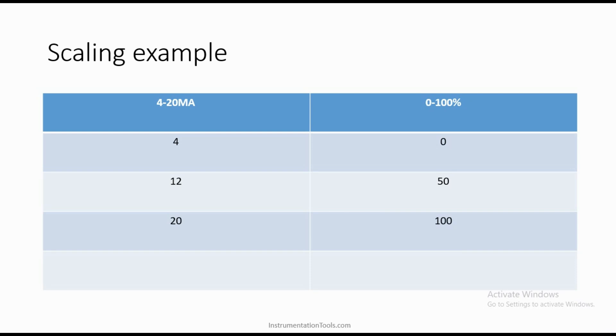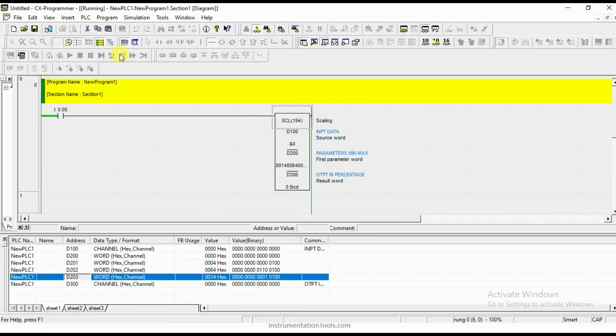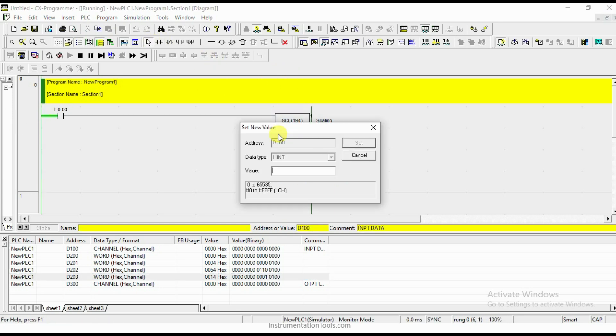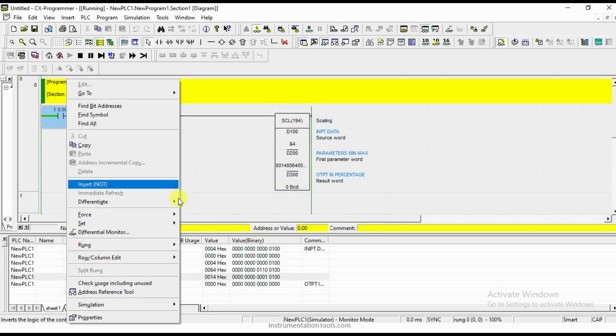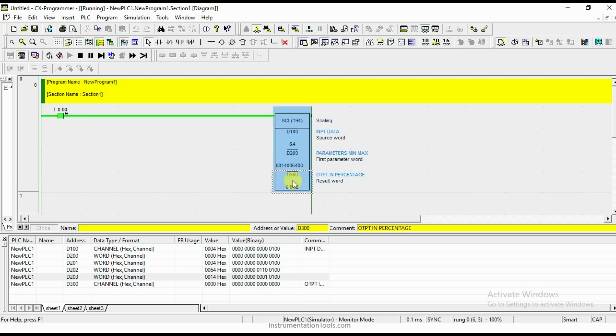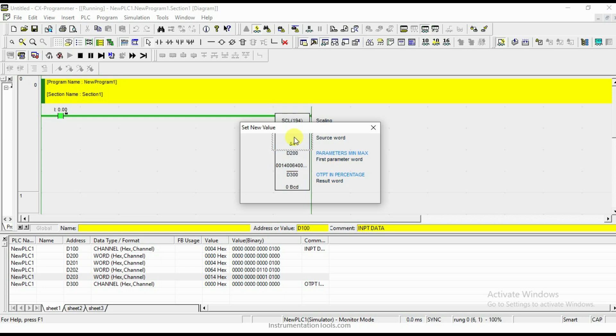Now the conversion is 4 to 20 milliamps to 0 to 100 percent. If the level transmitter is giving 4 milliamps, that means there is no water inside — that is 0 percent water. If the level transmitter is giving 20 milliamps, then there is 100 percent output. In between, 50 percent means half the water tank. So I will apply the input condition of 4 milliamps and check whether we get the correct output.